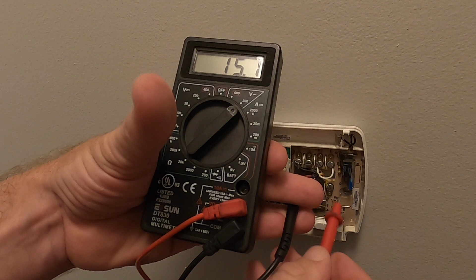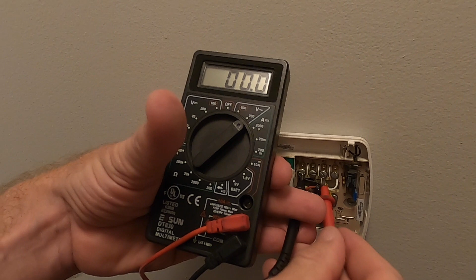In my case, the reversing valve will not have voltage because we're in cooling mode, but on most heat pumps you will actually have voltage in cooling mode and not in heat mode. It's just wired a little bit different. Yellow brings the compressor on outside. We got voltage on there. It's running to cool. And then the problem was again here in the auxiliary heat, in the emergency heat. Notice now we have no voltage, so we know that we've taken care of our problem. It's not calling for a defrost cycle, so to speak, like it was before, and we're back up and running with cool air.